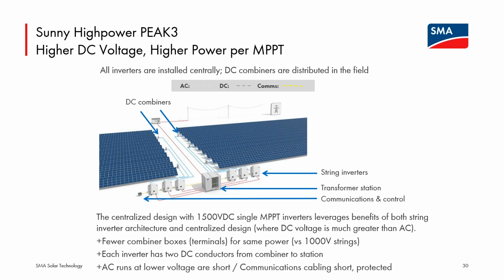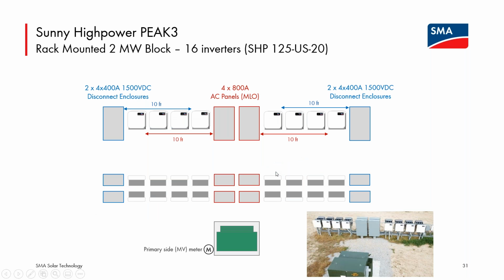And a final, almost afterthought for many folks: if the inverters are all very close to each other, the communications between them, even if forgotten in the design phase, are very easy to accommodate. If the inverters are spread throughout the PV array, and then we're getting close to commissioning, we need monitoring, and we didn't trench for the communications wires, it becomes very problematic. So hopefully communications is not an afterthought, but it is very easy to accommodate. So generally, even using more distributed power generation units, the centralized plant layout is almost always the SMA recommendation for utilizing the PEAK3.